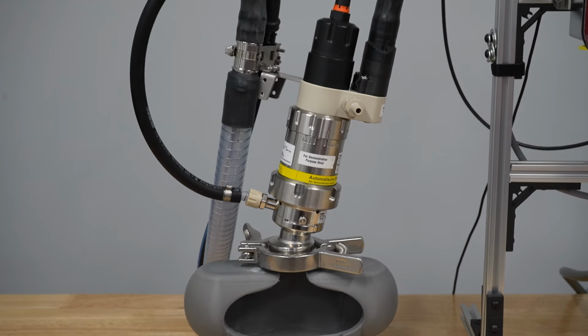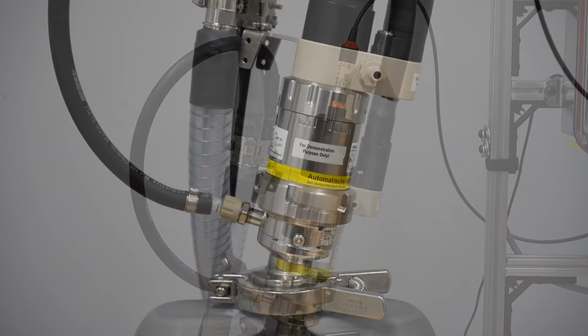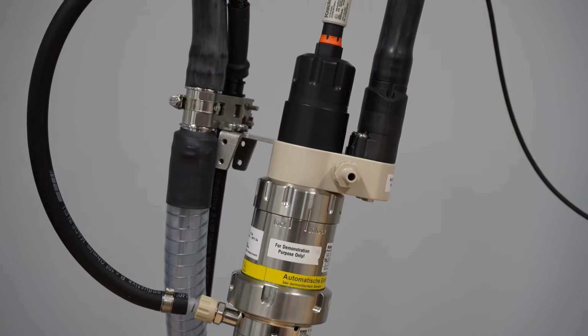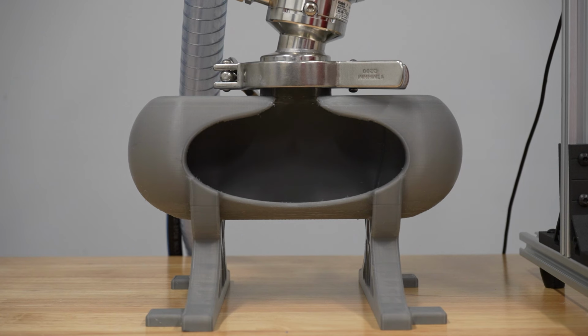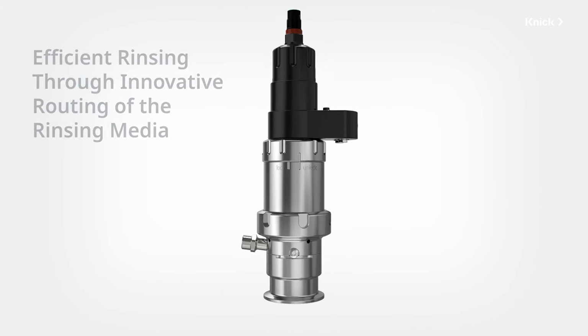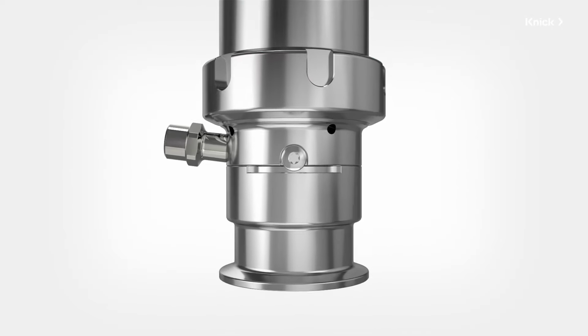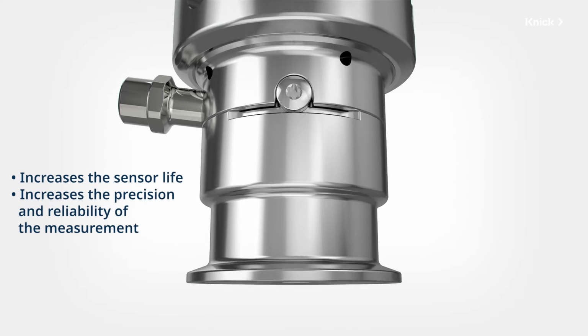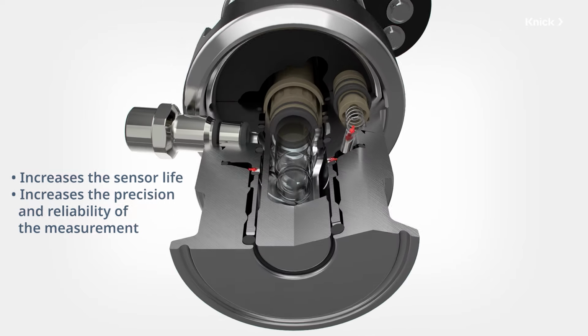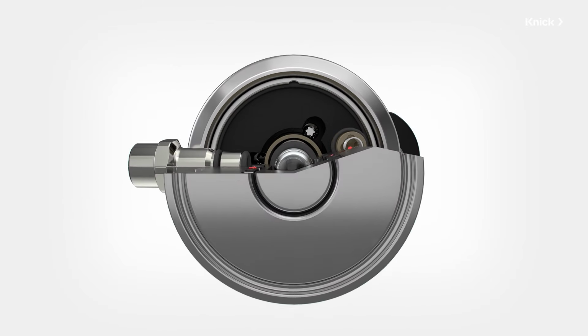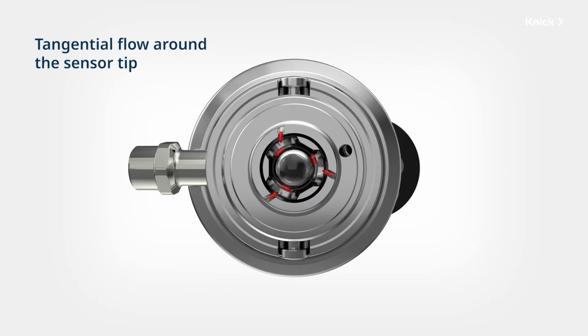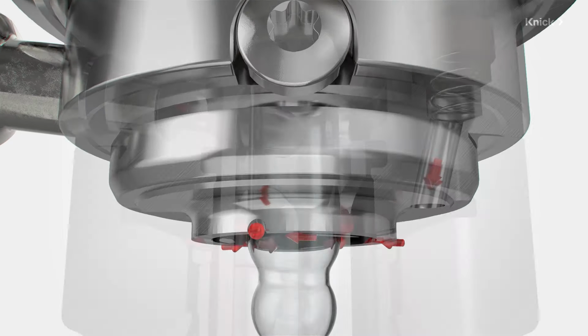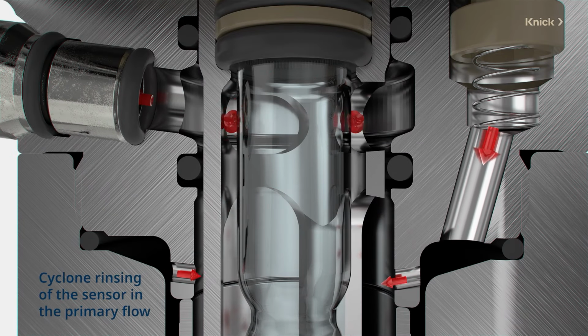The pneumatic retractable holder is the part of the cCare system that provides the user maximum process uptime. During an automated maintenance cycle, the pH sensor is retracted into the holder without interruption of the process. Isolating and draining the process pipe or tank is not required. All liquids needed to maintain the pH sensor, such as buffers, cleaners, and water, are delivered through the umbilical. This eliminates manual handling of the sensor, which in turn extends the life of the electrode versus manual maintenance procedures.